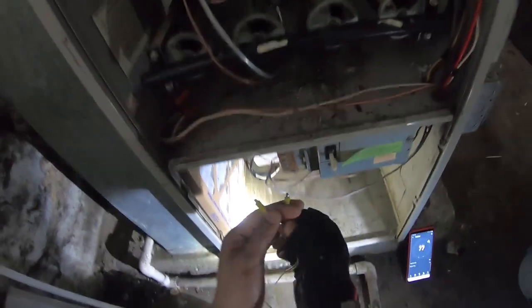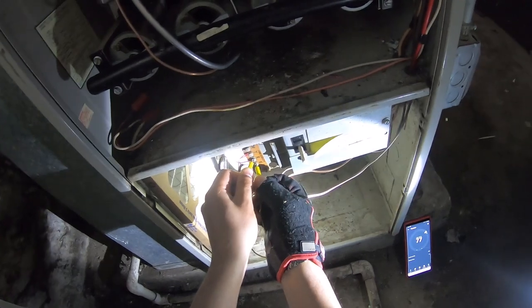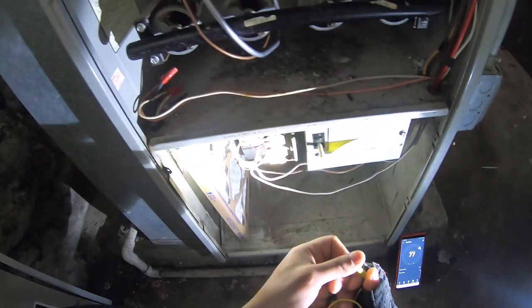We're able to turn everything on from down here, so we don't really gotta go to the thermostat. Lord, it's getting deeper, guys. Is it on? This thing doesn't even have a door switch. All right, you see these things? They're magnets. Check this out. The green one, I already know that's my fan. So if I give it this guy, the fan should turn on. Let's see. No, transformer's good, guys. Transformer's good.